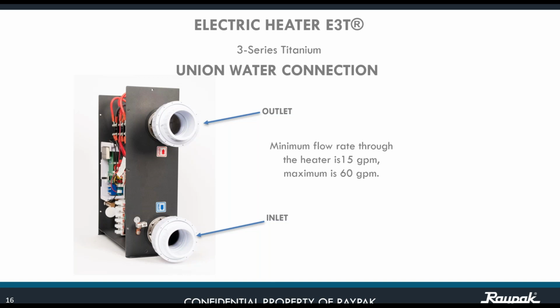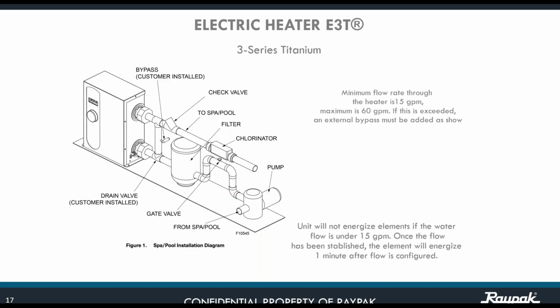Just keep in mind that the flow sensor is expecting to receive at least a minimum of 15 gallons per minute. So if you do the proper bypass installation, as should be the norm really, anytime you have a heater, you should put in your bypass, and if you want, a flow meter at the entrance of the unit. If you have a flow meter, you can monitor the situation more. But don't worry about that, because if you don't have a flow meter, or you don't want to install one, the unit itself is going to give you that information. The unit will not energize the element if the water flow is under 15 gallons per minute. Once the flow has been established completely, the element will energize, and there is a built-in 1 minute delay in the CPU.